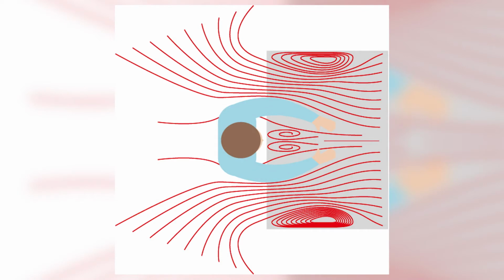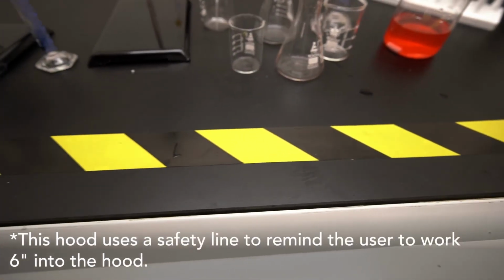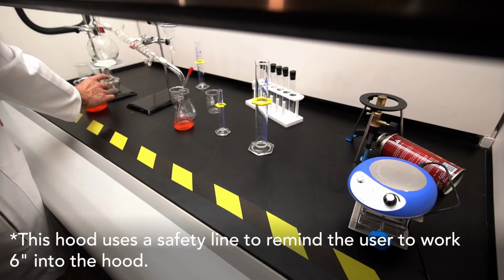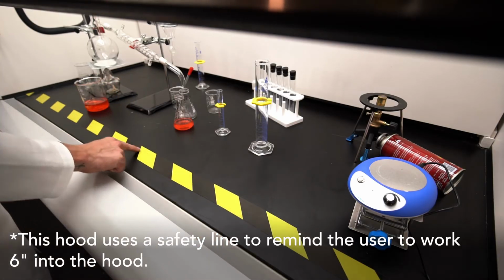In the lab, we never work with an empty hood, and we never have room conditions that are perfect. Room conditions are changing minute to minute, even in the best labs. In fact, in a lab building, the airflow in individual rooms resembles ocean currents with tides and ebbs, continually moving and changing. Your body also causes turbulence. When you stand in front of a hood, your body acts much like an airplane wing. There is a low pressure area created in front of you. This low pressure area can suck out chemicals from the hood. That's why we work 6 inches into the hood, so the chemicals are less likely to be drawn out. The critical 6 inches allows the hood to contain at a much better rate.